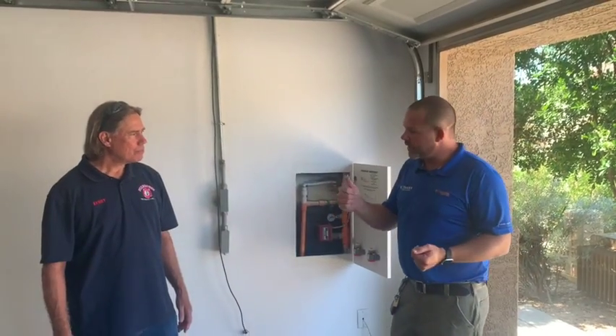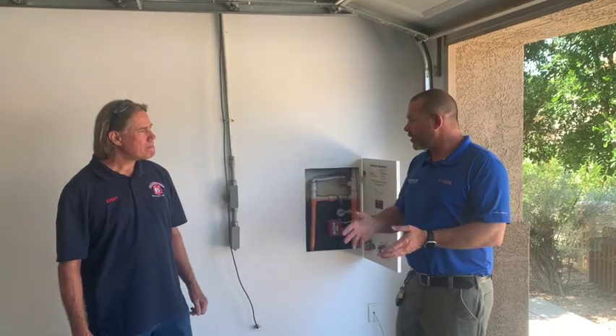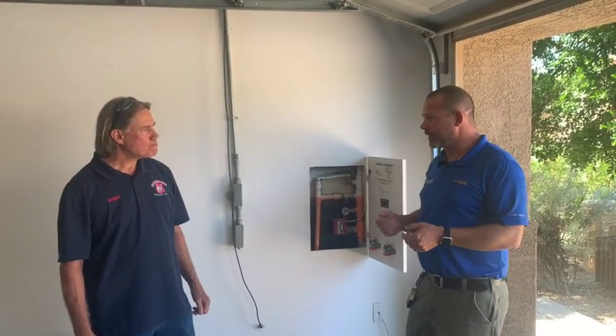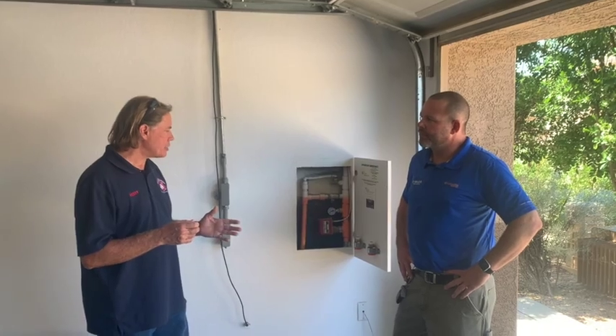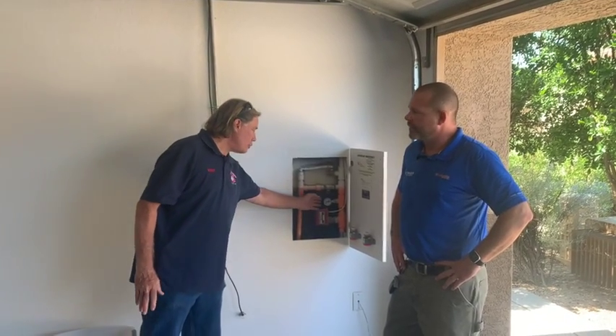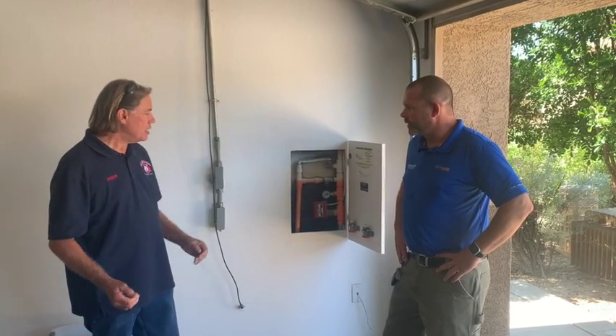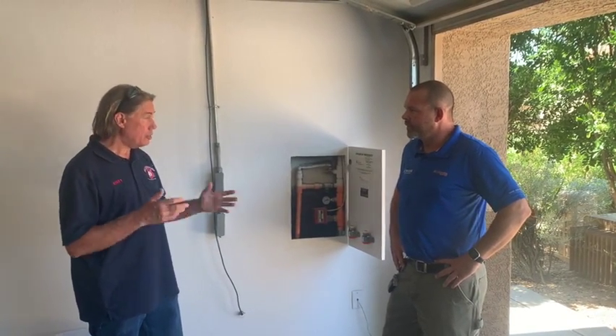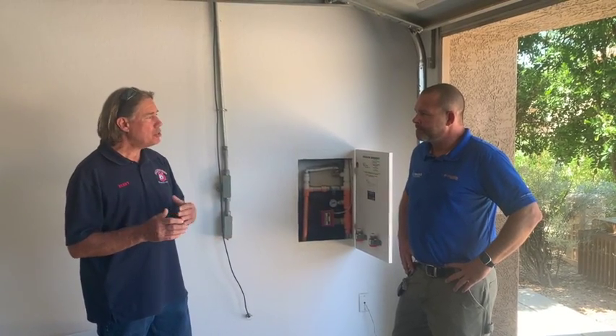Wonderful. All right, so Kerry, you explained to us about the homeowner maintenance, but as far as professional maintenance, how often should we have professional maintenance done on our fire suppression systems? Well, as the city doesn't really have any codes requiring maintenance on fire sprinkler systems in a residential setting, they do in commercial, but for residential, there is no real code requiring maintenance schedules. I prefer to leave it up to the homeowner, but I'll discuss it with them in such a way as I will say, well, at least every 5 years, if you have a gauge, we need to come out and change that gauge. In the meantime, if you're maintaining your system properly and you're keeping an eye on everything, that's up to you, up to your comfort level.